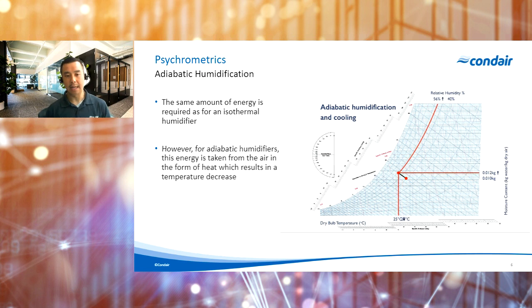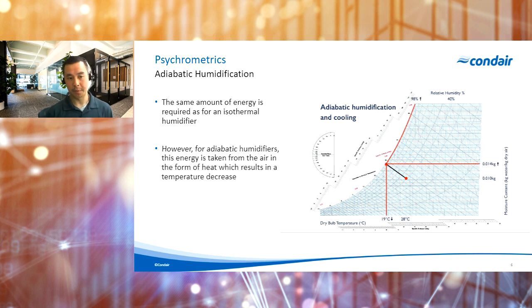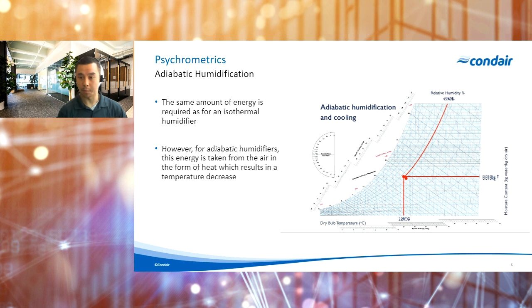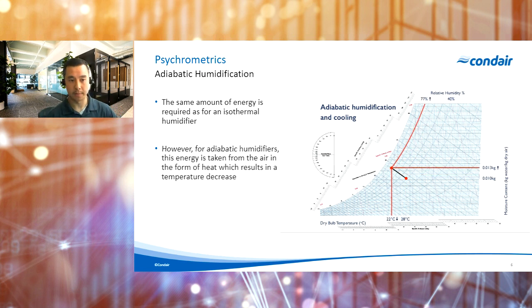If we look at the adiabatic process to start on a psychrometric chart, it's essentially a constant wet bulb process. Because we're pulling energy from the air, in addition to an increase in humidity, we also have a cooling effect. It ends up being about 0.3 kilowatts of cooling per pound of water that we're evaporating. This is one of the main reasons why this is such a great technology and such an efficient way to cool and potentially humidify a data center, or really any application that requires year-round cooling as well as potentially some level of humidification.